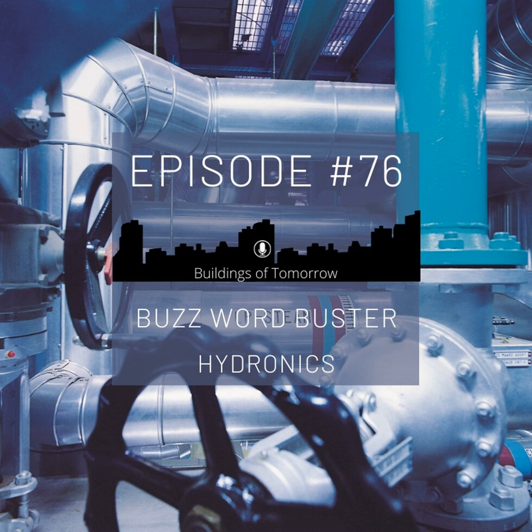Okay, so the maximum flow is, as I said before, something we can set on such a PICV. It's a mechanical setting, and it ensures that we get the right maximum amount of flow, and by that we do hydronic balancing. So if the installer sets that maximum flow on every PICV that he puts into the hydronic circuit, the system is already balanced. And it's much less effort to do it at this point in time than with traditional valves, to go back and do it when the total installation is finished. And that's also a big time-saving effort, as we have seen in many projects.